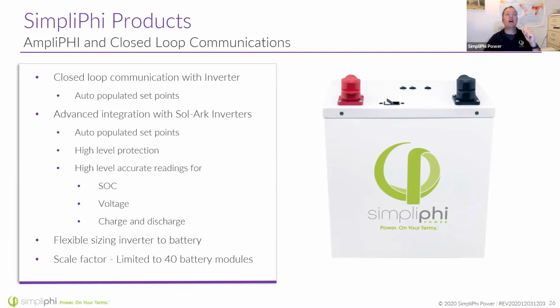With the standard Phi batteries, I always want to see that C/2 rating, since it's hard for an inverter to limit its power output to AC loads. But if you have equipment that we know is able to communicate, you could go ahead and, instead of having that 8,000 watt Radian needing 16 kilowatt hours of batteries, have maybe one battery on a Sol-Ark 8K or 12K, or two batteries on a Sol-Ark, because the SimpliPhi batteries will communicate and tell the Solar there's only one or two of us here, don't discharge or charge faster than we're capable of handling. That allows you to approach a homeowner with a smaller battery bank than initially planned and get them up and running with critical loads panels.